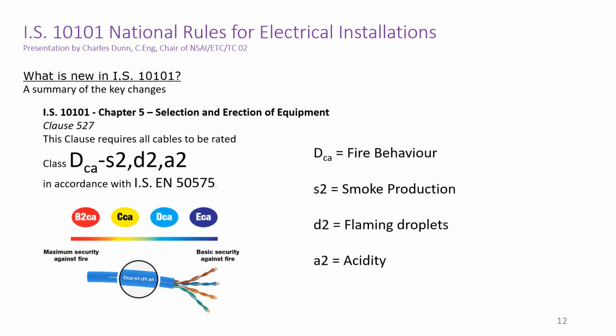Moving on to the next slide, we find another big change and one for the better. Chapter 5, Selection and Erection of Equipment, Clause 527, now requires all cables in buildings to be rated Class DCA, S2, D2, A2, in accordance with EN 50575. Lots of letters and symbols, but what does it all mean?